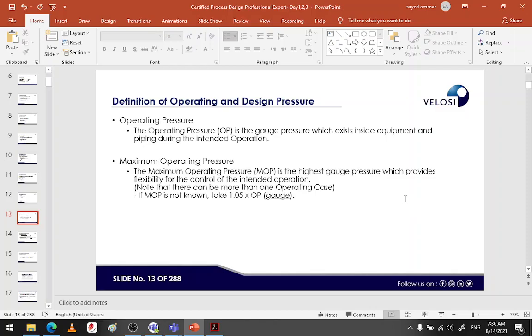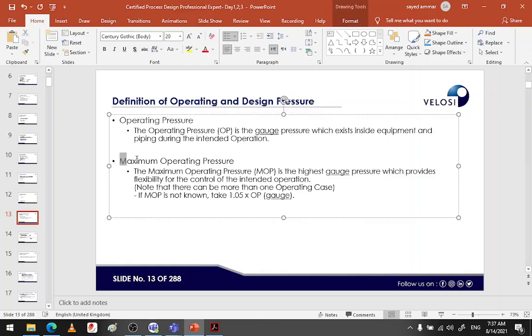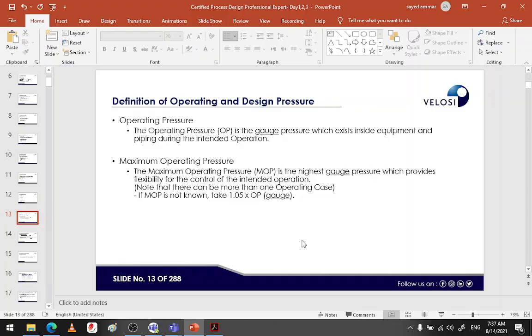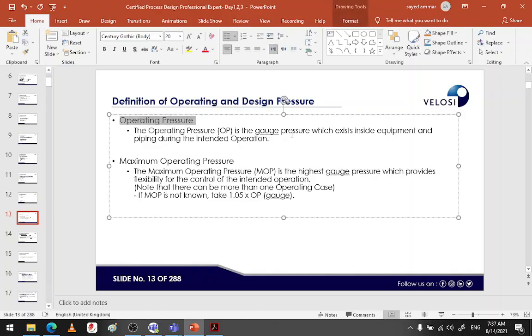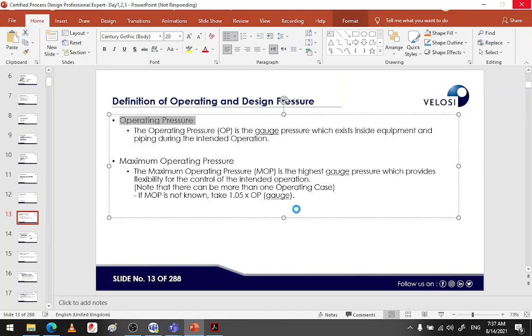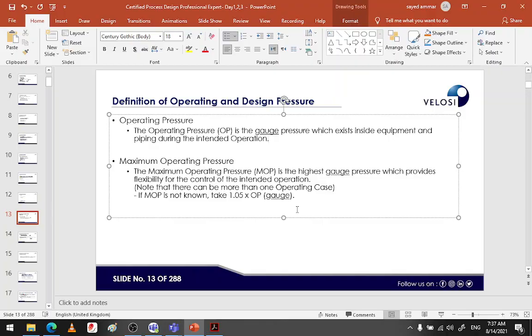The most important part we are going to identify today is to define the operating pressure and the maximum operating pressure. Operating pressure is the gauge pressure which exists inside the equipment and piping during the intended operation. How many bars, how many psi you have from your fluid. Maximum operating pressure is the highest pressure which provides flexibility for the control of the intended operation. If the maximum operating pressure is not known, take 1.05 from the operating pressure.